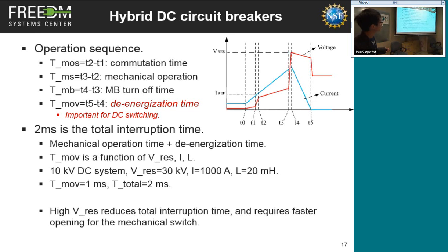So the voltage will very quickly increase to a high level in a few microseconds. At that moment, your mechanical switch should be able to withstand that voltage. Otherwise, there will be a pre-strike. Otherwise, there will be an arc and you fail. So, and after that, what happens?